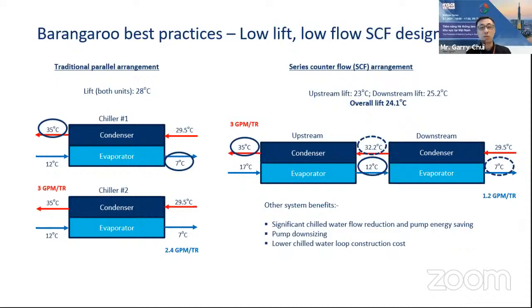So on average, these two units will be at 24.1, which is about 4 degrees C less than the traditional parallel arrangement. And this 4 degrees C of lift or temperature reduction would translate into something like a 10 to 12% efficiency improvement. And in addition to the chiller energy efficiency, this series counterflow arrangement also helps on the pumping side.